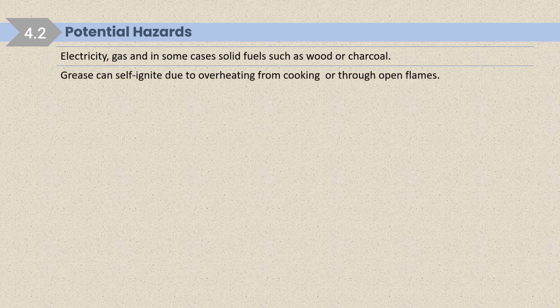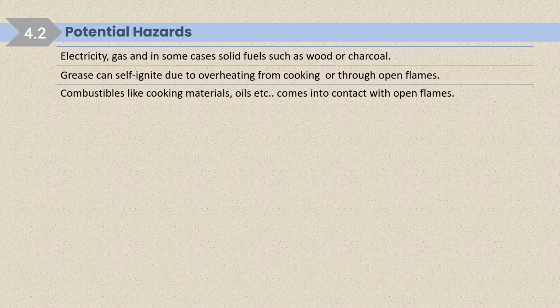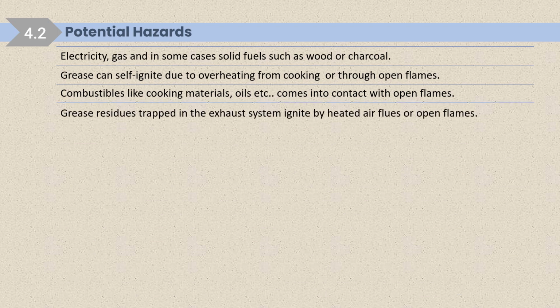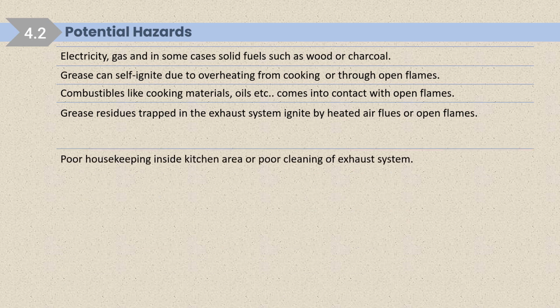Grease can self-ignite. Grease is also a potential hazard. So grease can self-ignite due to overheating from cooking or through open flames. Combustibles like cooking materials, oils, etc. come into contact with open flames. Grease residue trapped in the exhaust system can ignite by heated air, flues or open flames.